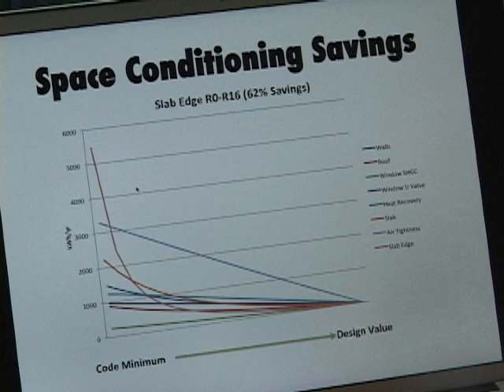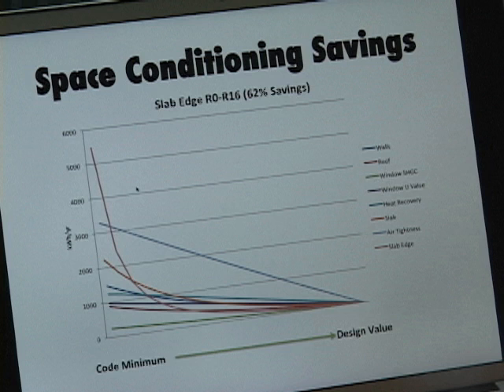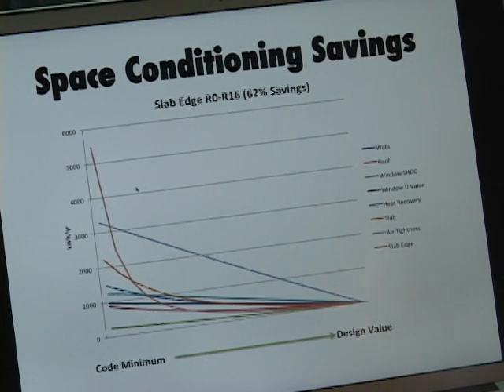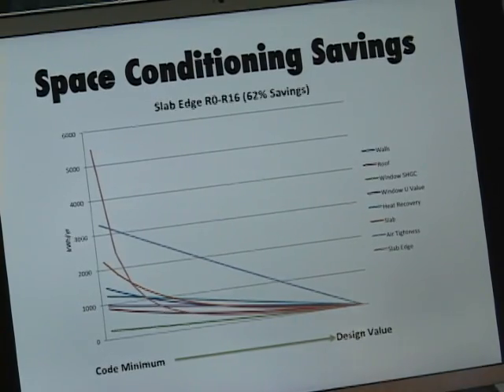You can get a sense of which things made the most difference from code minimum to Passive House. Slab from R0 to R16 — 40 percent reduction. Air tightness from 6 down to 0.4 — 50 percent reduction. Slab edge insulation from R0 to R16 — 62 percent reduction. It's interesting to see the relative value of these things. In the case of slab edge insulation, it's a relatively easy thing to do and it made an enormous difference. You can make a pretty easy case for what people may see as absurd levels of insulation.